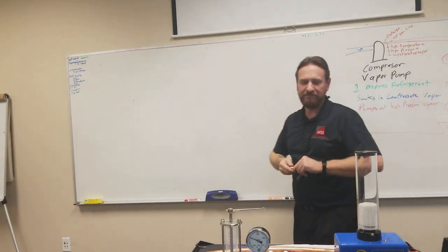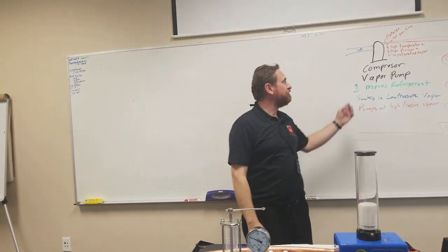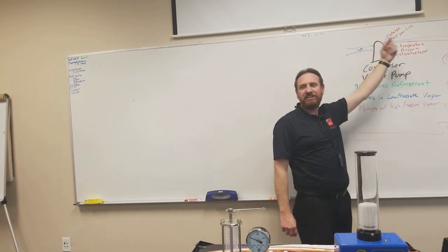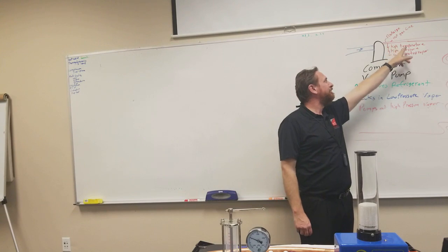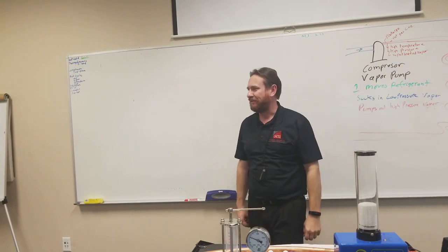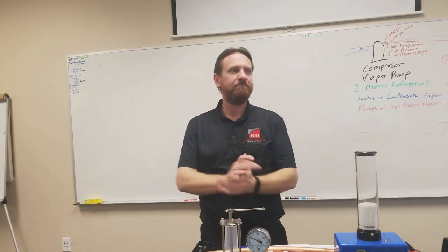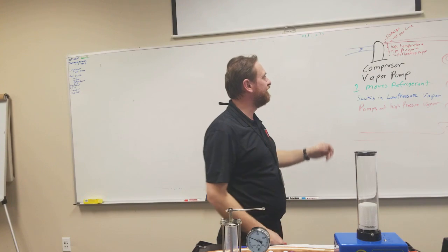We're not ready for that yet, but if we put that word in there now, when we get there it'll make more sense. So the refrigerant coming out of the compressor, that smaller line, the discharge line, also a hot gas line, is a high temperature, high pressure, superheated vapor. So far so good? It's the shortest line of the whole system.